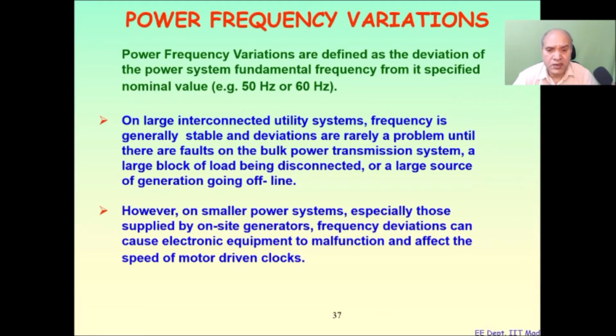However, it varies depending upon the power mismatch or power balance between the generation and the load of the active and reactive powers. Okay. Now, what happens when the frequency is varying out of the limits that is prescribed by some standards? Then we need to act upon it through the governor action. Governor action is nothing but it matches the real power requirements to maintain the frequency. Okay. So this is another important aspect in power system.